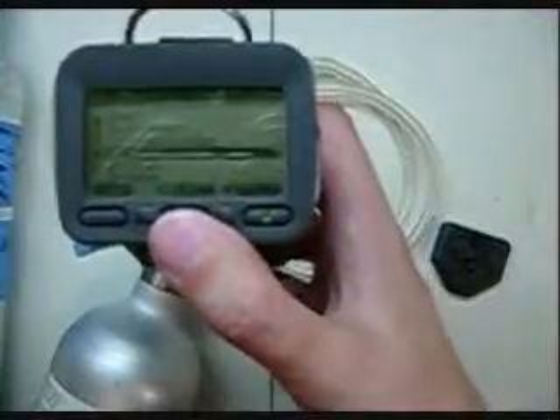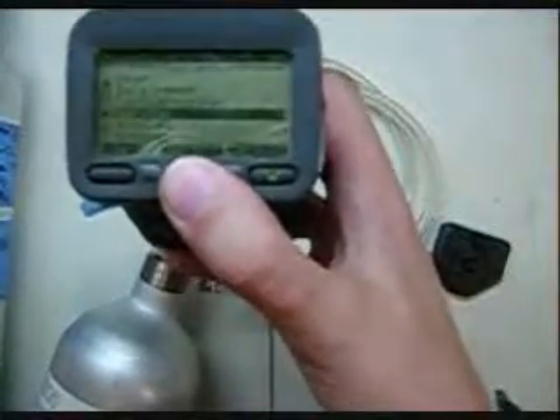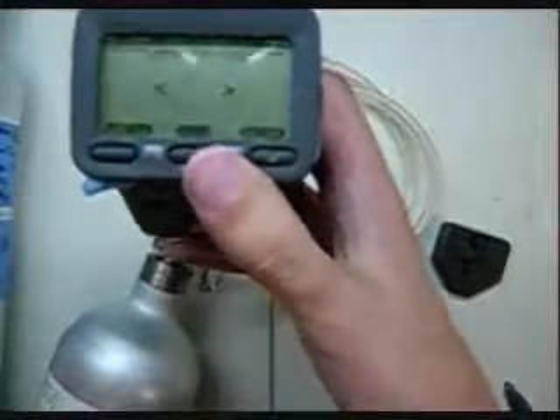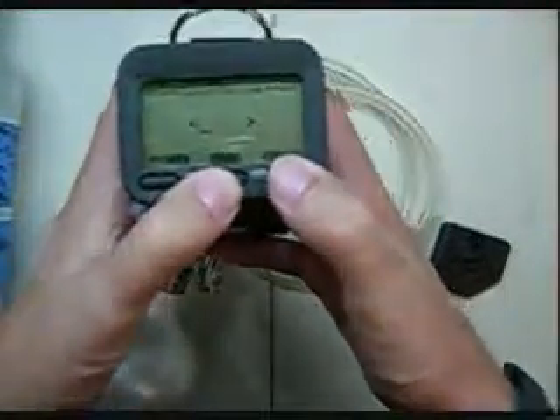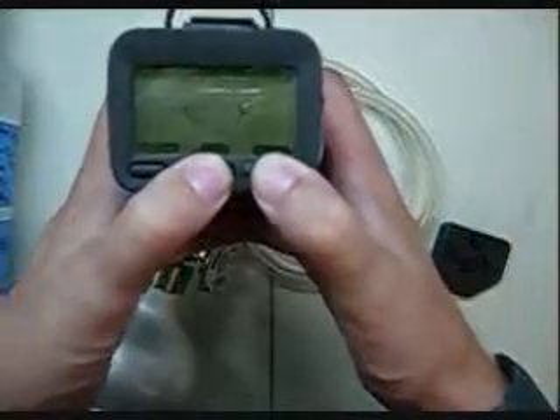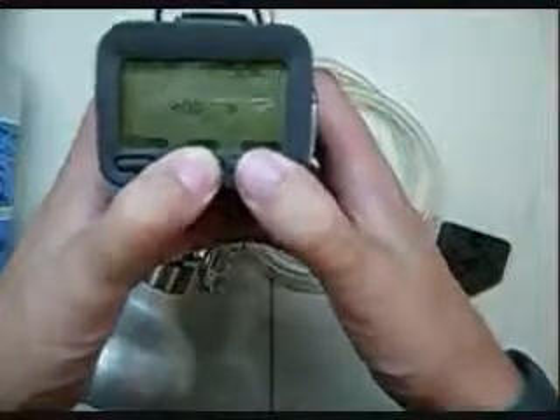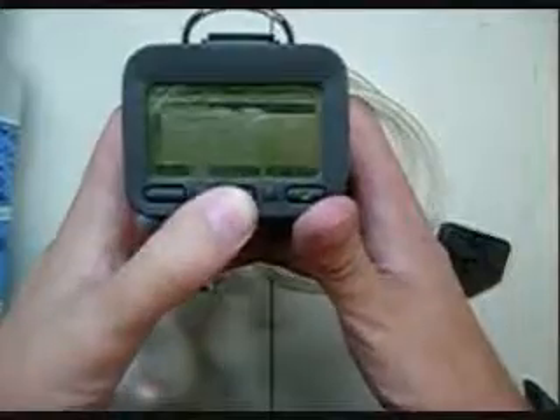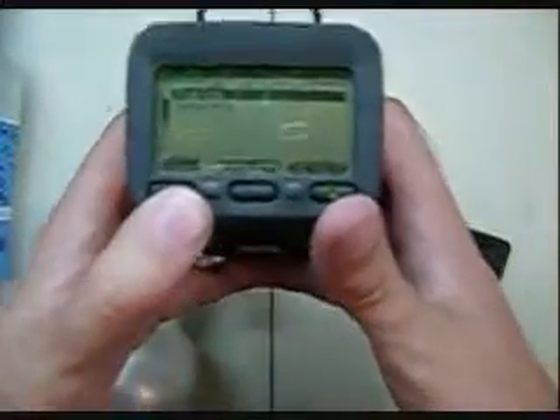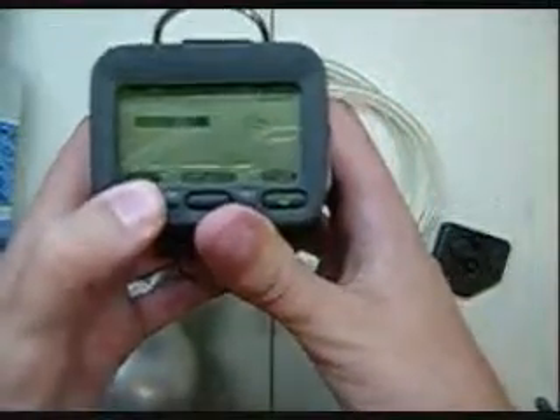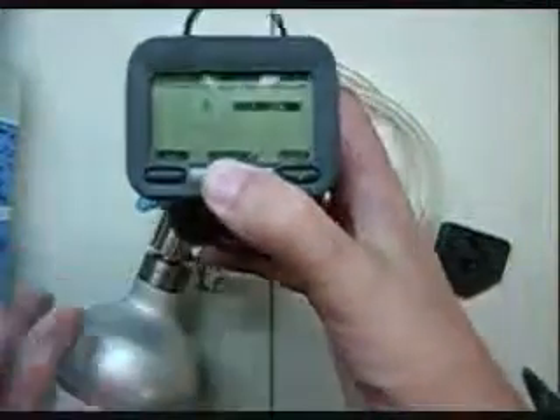Next up, you're going to hold down this middle button again. Now we're going to actually calibrate this monitor. You're going to go to service, not auto calibration, because the ammonia and the SO2 sensors won't do the auto cal as easily. So select. It's going to ask you for a security code. The security code is 0, 0, 1, 1. Again, that's 0, 0, 1, 1. Press the middle button, and it'll bring up a service menu. Hit down once to go to sensors, and we're going to start with the methane sensor.